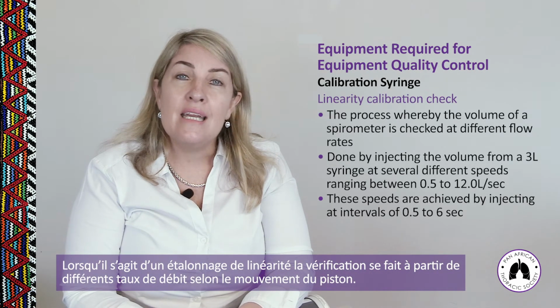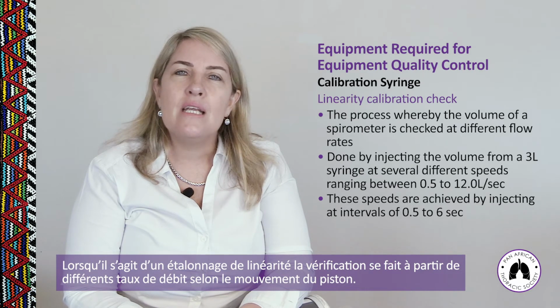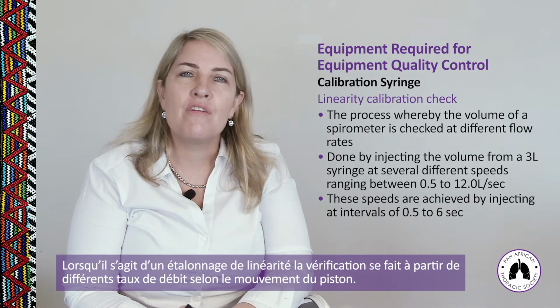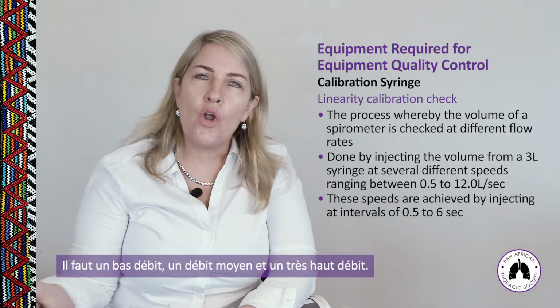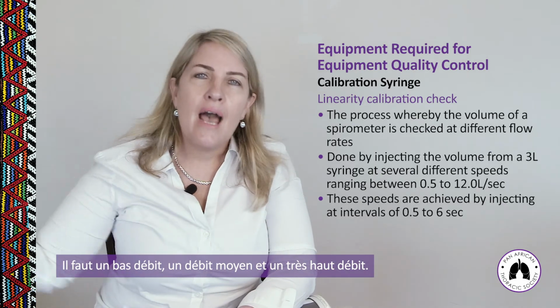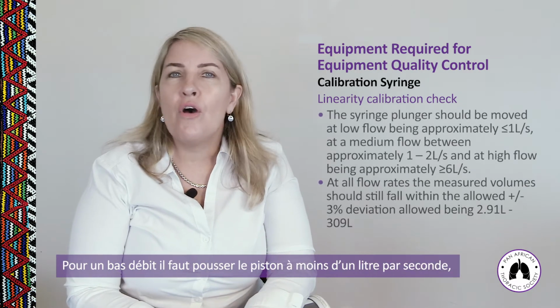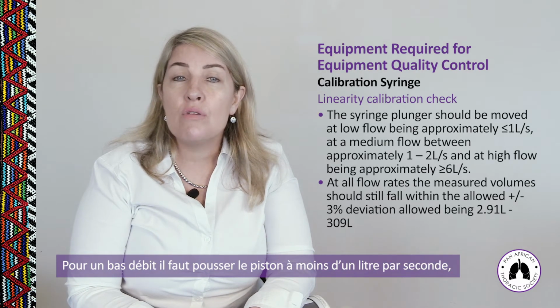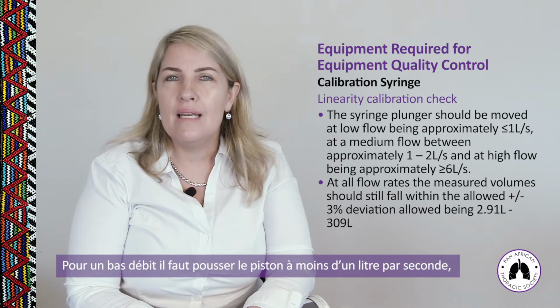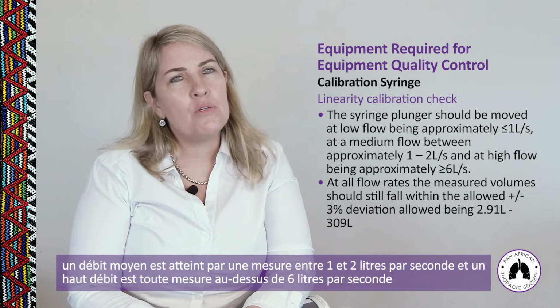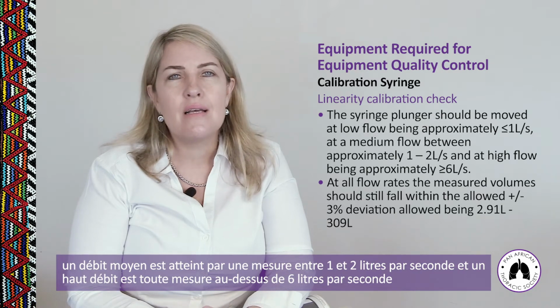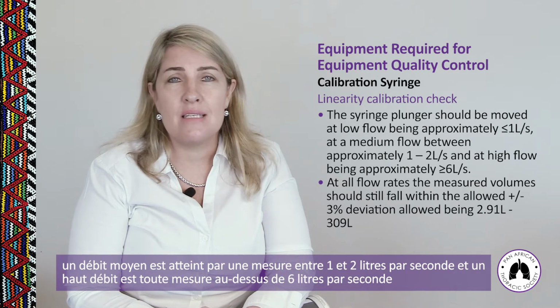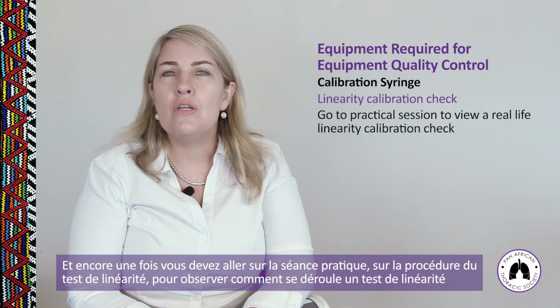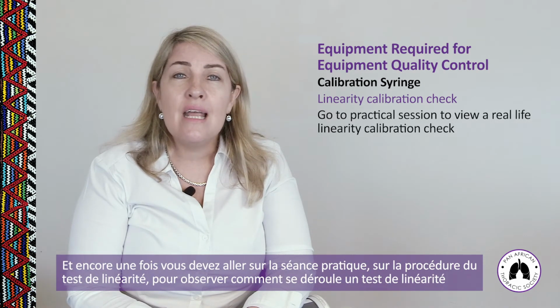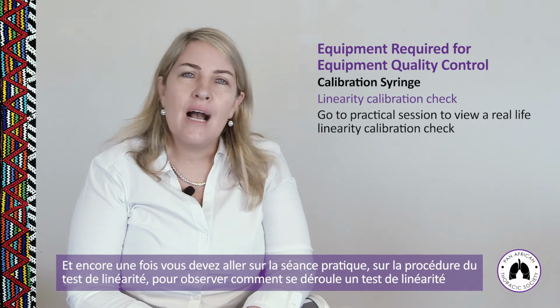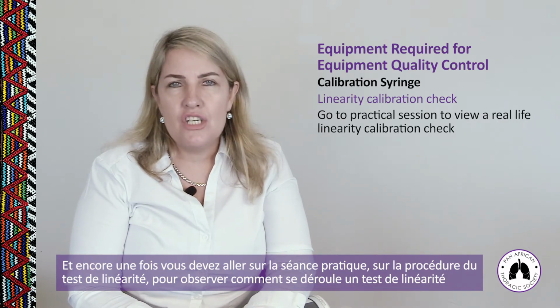When you look at a linearity calibration check, we now need to move the syringe plunger at different flow rates. We need to move it at a low flow, a medium flow, and a very high flow. A low flow in linearity checking is moving your syringe plunger at less than 1 liter per second. A medium flow is between approximately 1 to 2 liters per second, and high flow is anything above 6 liters per second. And once again, you need to go to the practical session on linearity testing to see how a practical linearity check is carried out.